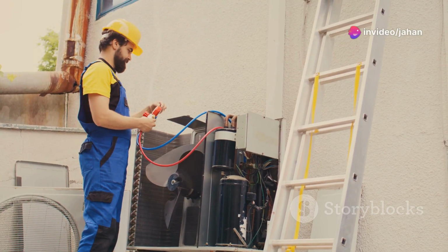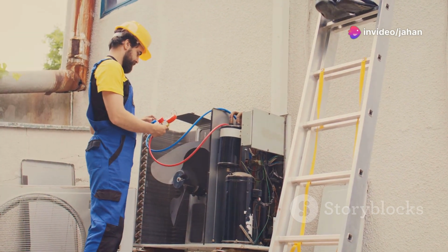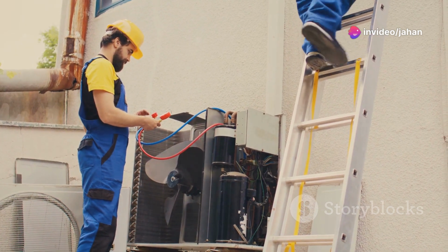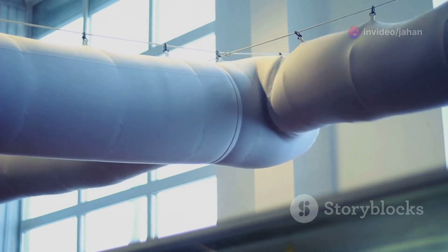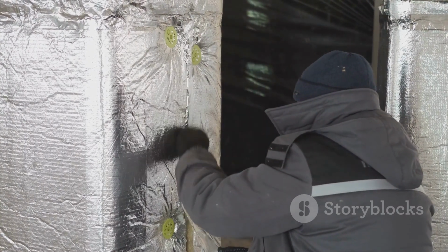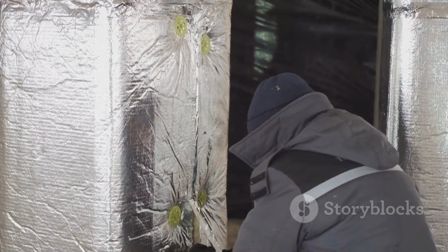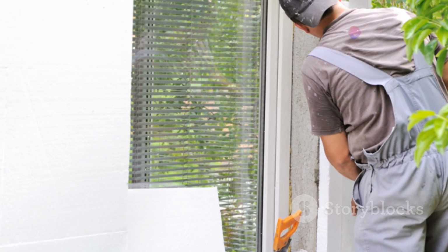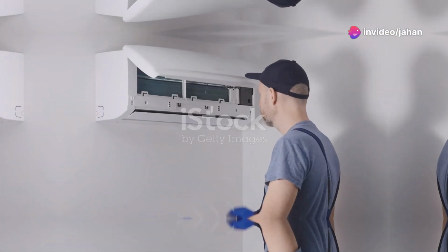Connect the ductwork to the indoor unit and seal all connections with foil tape. Don't use duct tape. It dries out and loses its adhesion over time. Insulate the ductwork to prevent condensation and energy loss. Use R-value insulation that meets local building codes.